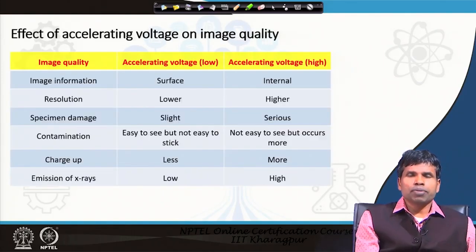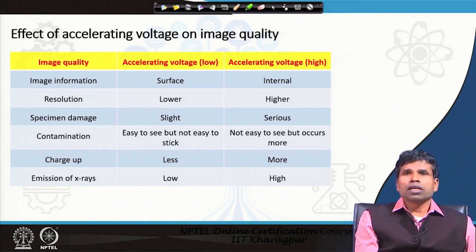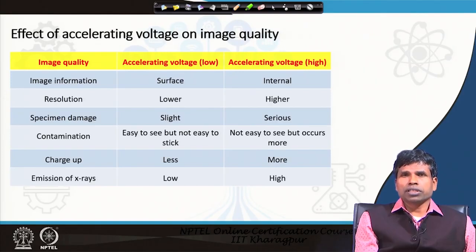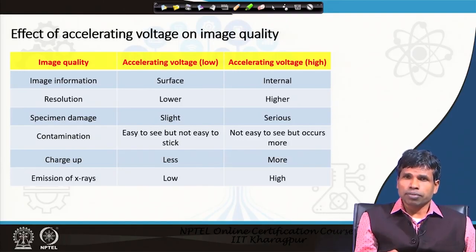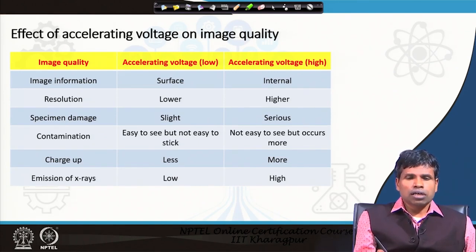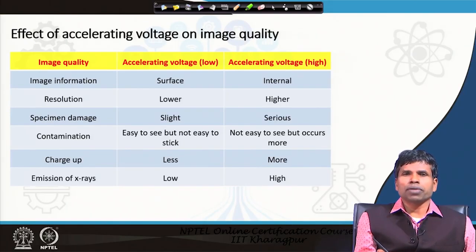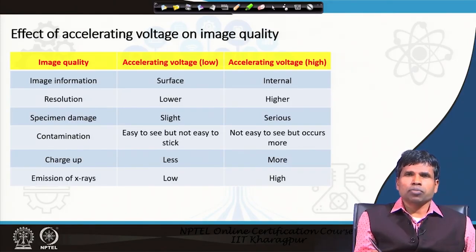Let us discuss the effect of acceleration voltage on image quality. If we increase the acceleration voltage, the interaction volume changes — higher acceleration voltage means the beam will penetrate more depth into the specimen, so information will be collected from a larger volume. Second, as we increase acceleration voltage, the yield of backscattered electrons and secondary electrons will also increase.